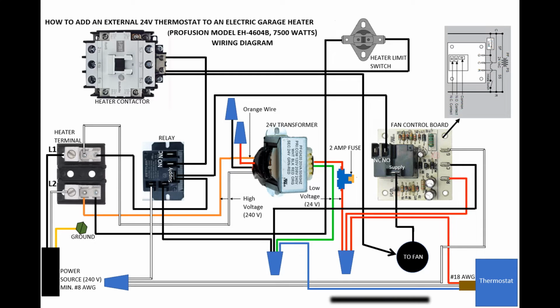Now on the other side of the transformer, you have low voltage wires, red and green. The green wire is connected to the common terminal of the relay, the fan control board, and the thermostat as shown here. And the red wire is connected to the red terminal of the fan control board and the R terminal of the thermostat as shown here, basically to deliver power. So this is how we're going to rewire a heater.